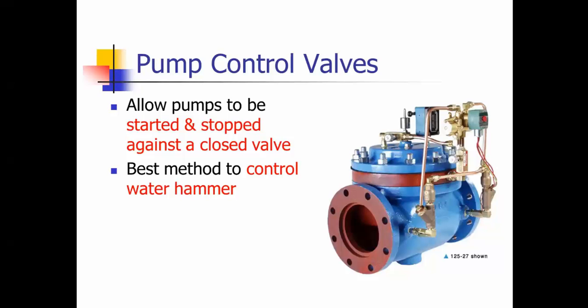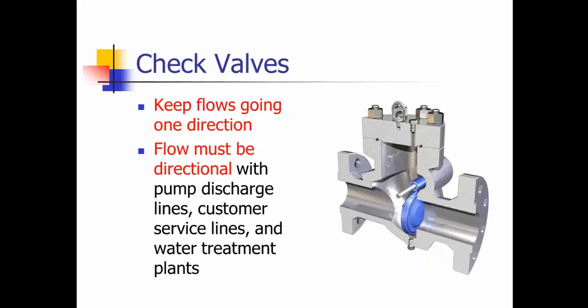This is a pump control valve, and they allow the pumps to be started and stopped against closed valves. It's the best method to control water hammer. If you look on top of this regulator, when the pump is energized, the water is bled off the top, and this slowly opens and it trips this switch here. And so it's essentially a closed valve. And when this gets all the way open, it trips that switch, and then when you shut it off, the pump continues to run, and this slowly gets water on top of the bonnet, and then it slowly drops down until it trips that switch, and that's what shuts the motor off. So essentially you're starting and stopping the pump against a closed valve.